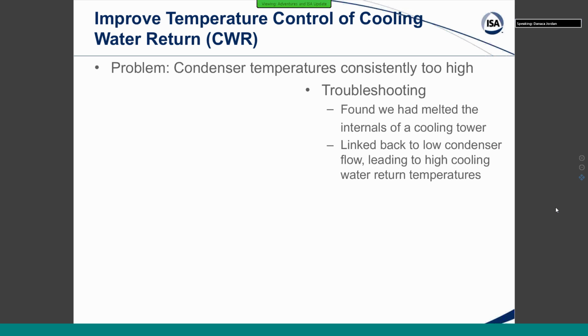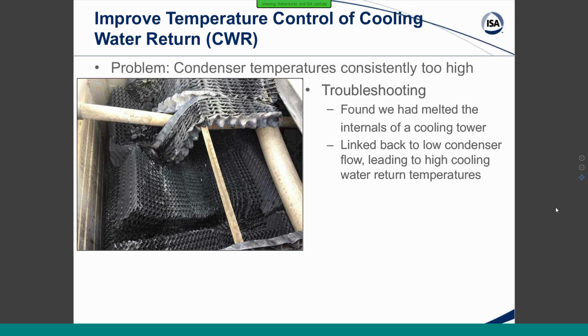Okay. This project here, we are looking at control of our cooling water return temperature. What we found, actually during an alarm management meeting, as we were trying to figure out why all of our condenser temperatures were so high, is that we had managed to melt all of the internals of one of our cooling towers. If you have plastic cooling towers, which you can see we do here, this is very, very possible. I've actually also set a cooling tower on fire. There are many things that you can do to cooling towers that I did not know were possible.